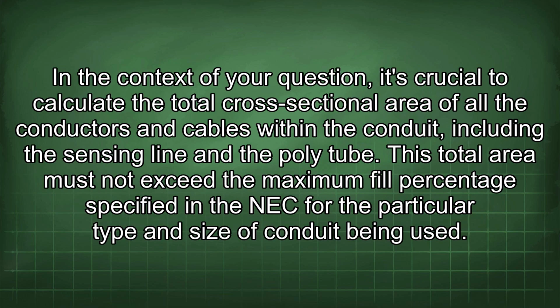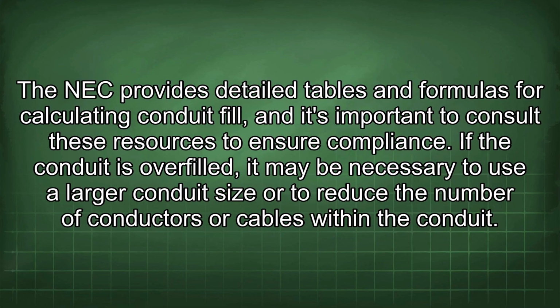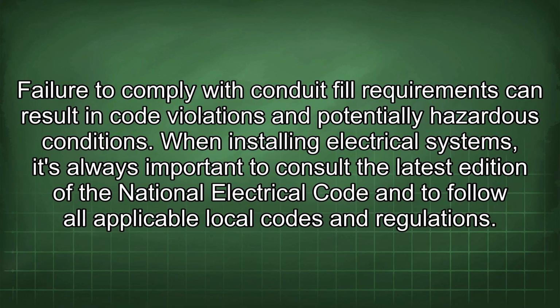In the context of your question, it's crucial to calculate the total cross-sectional area of all the conductors and cables within the conduit, including the sensing line and the polytube. This total area must not exceed the maximum fill percentage specified in the NEC for the particular type and size of conduit being used. The NEC provides detailed tables and formulas for calculating conduit fill, and it's important to consult these resources to ensure compliance. If the conduit is overfilled, it may be necessary to use a larger conduit size or to reduce the number of conductors or cables within the conduit. Failure to comply with conduit fill requirements can result in code violations and potentially hazardous conditions.